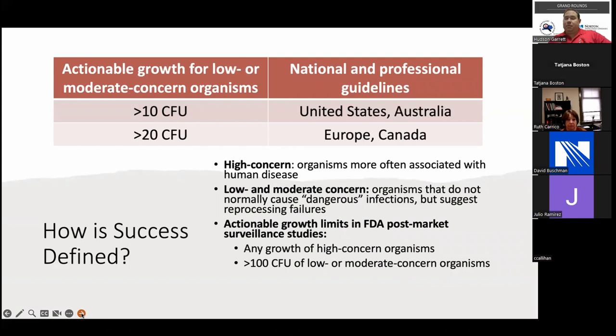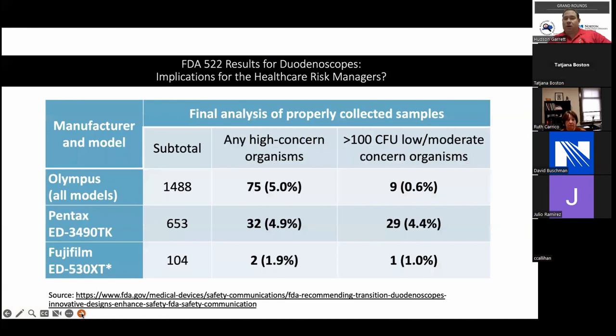And then the more high-risk bucket, they called high concern, right? The FDA's expectation, frankly, was that there would be zero. Now, keep in mind that this class of medical devices is not sterile—it's only a semi-critical device, so it's reprocessed using high-level disinfection. So the thought of something that is not even treated as a sterile device, is not sterilized, being held to zero by the FDA was way off the mark. So what they ended up with was less than 10, but zero was really the goal they were trying to accomplish.